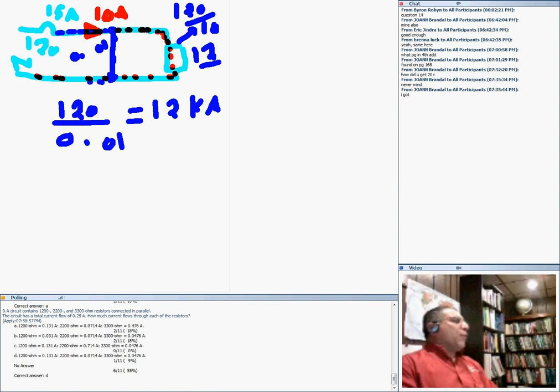I probably should get rid of a zero to make it more realistic — so 0.01 instead. Divide 120 by 0.01 impedance and you get 12,000 amps. That's the short circuit — that's what you see with a short circuit.